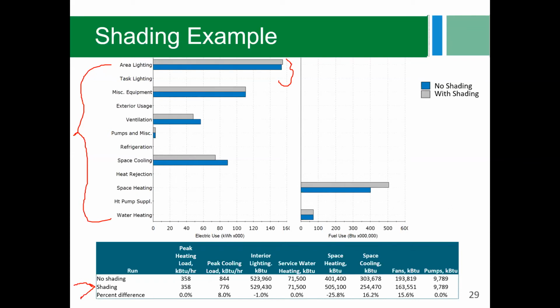In terms of this example, you can see the peak cooling load was reduced from 844 kBTUs per hour to 776 kBTUs per hour with the shading. So there was a nice reduction in peak cooling load. But then we saw a large, see this here, 25.8% increase in space heating energy usage, and a 16.2% decrease in space cooling energy usage. So this is quite an impactful one. And the same with fans, quite a reduction in fan energy, because this is an office building and it's very much affected by cooling, and the fans are not going to operate as much if the cooling load is less, potentially. Anyway, this is the type of analysis that you would do for the simple box modeling cycle.